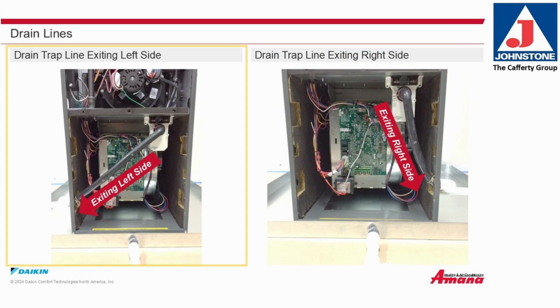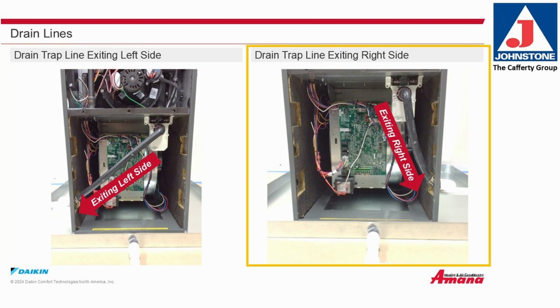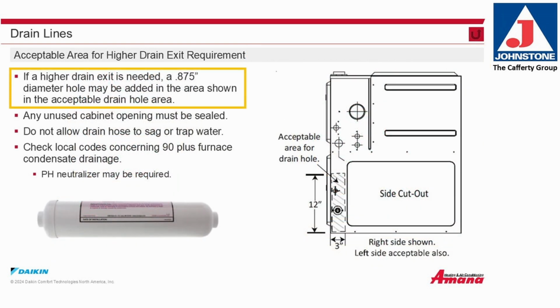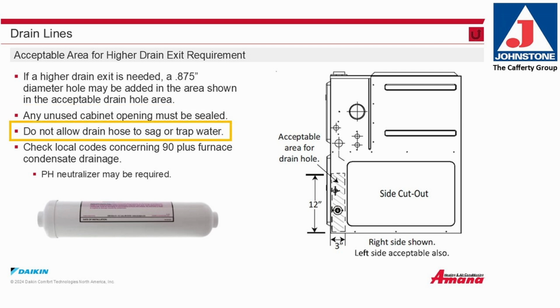Drain lines. Here is an example of the drain trap exiting the left side of the furnace. Here is an example of the drain trap exiting the right side of the furnace. If a higher drain exit is needed, a 0.875-inch diameter hole may be added to the area shown in the acceptable drain hole area, shown on the diagram on the right. Any unused cabinet opening must be sealed. Do not allow the drain hose to sag or trap water. Check local codes concerning 90-plus furnace condensate drainage. Depending on environmental conditions, pH neutralizer may be required.